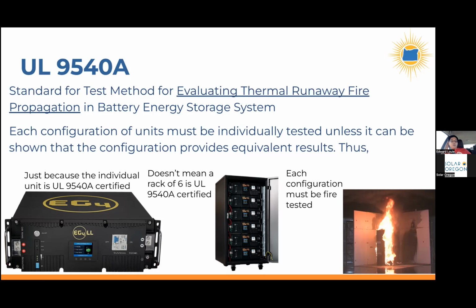And this test is very specific, because if you were to test an individual module, for example one of these rack mounted batteries, what you'll get is a report that tells the findings from that module, that one rack mounted battery. Now, if you were to then sell that battery in a server rack where you put 6 of them, that does not mean that the server rack with 6 batteries is UL 9540A certified, because it's a different configuration. And so for the UL 9540A test, you can find test results for both the single server rack battery, for example, and then if the company chooses to test a 6 battery in a rack configuration, they can have a separate 9548 certification for that setup.